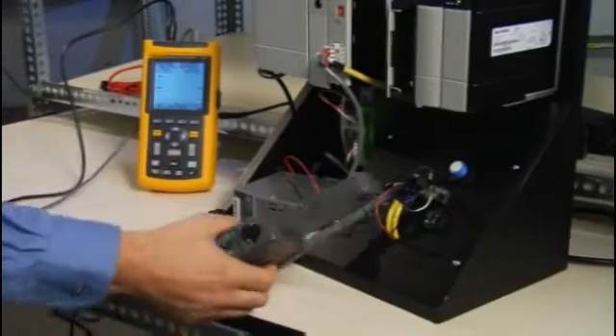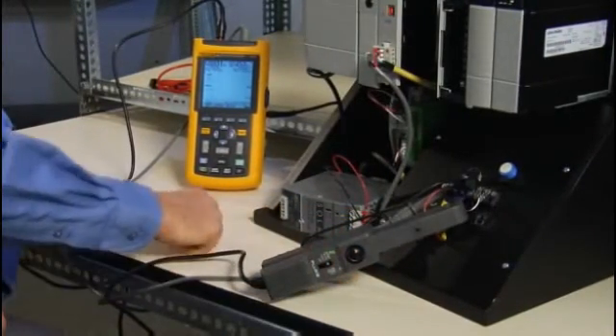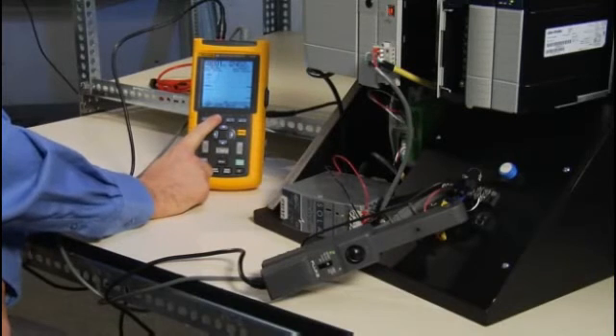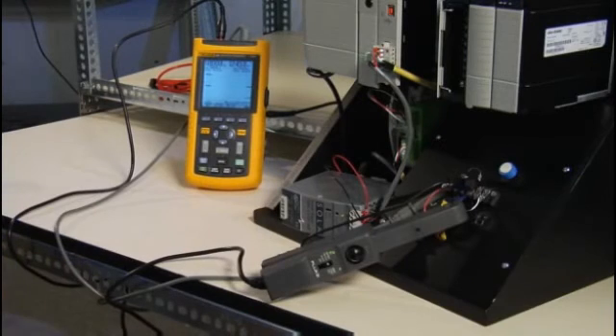We'll connect channel A using a current clamp across a DC supply conductor and channel B across a DC output voltage. With the Scope Meter, we could plot this over time so we can see the load current changes.